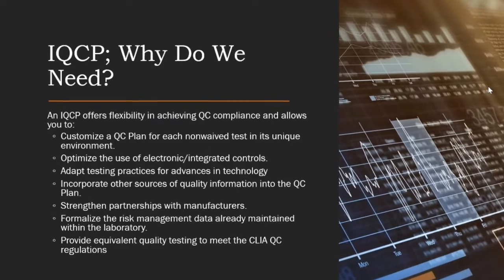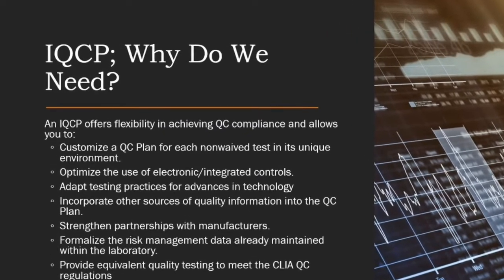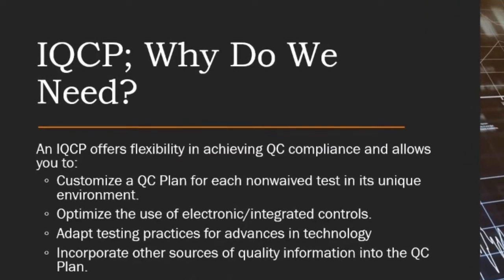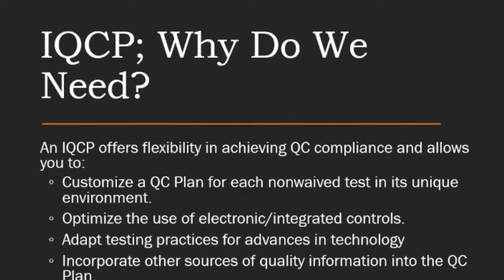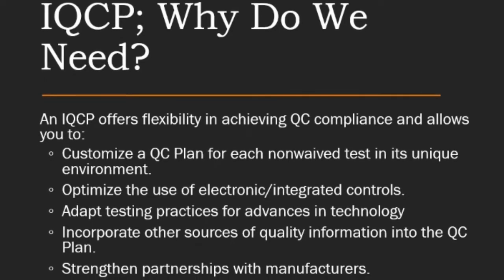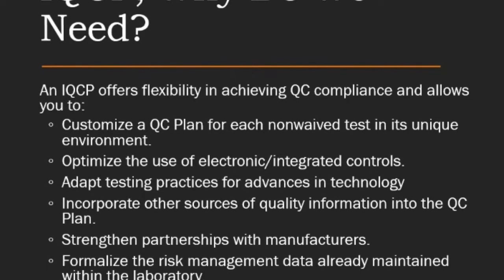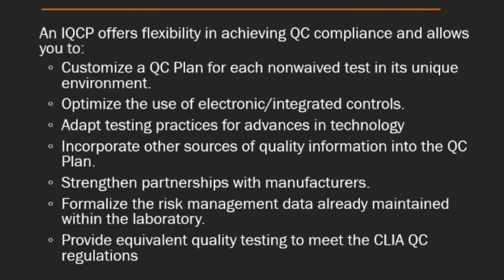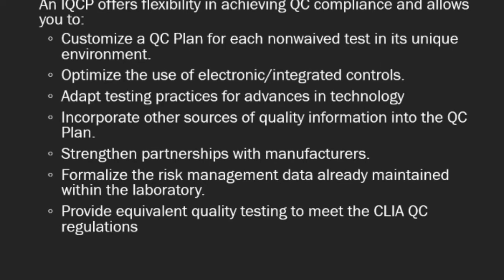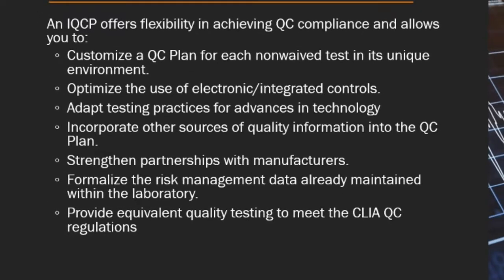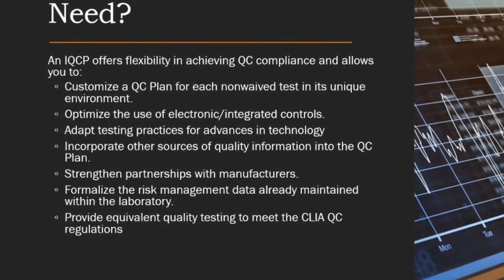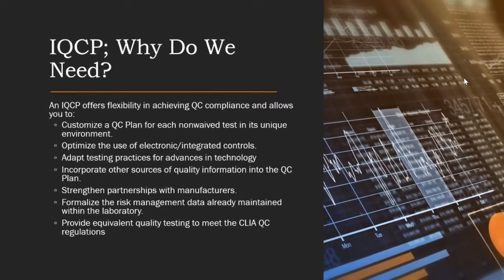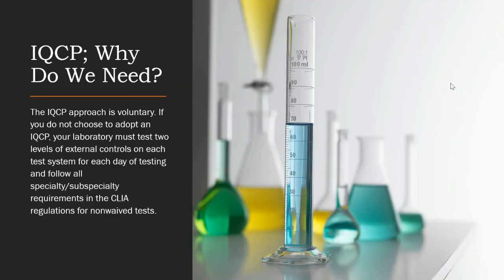An IQCP offers flexibility in achieving QC compliance and allows you to customize a QC plan for each non-waived test in its unique environment, optimize the use of electronic and integrated controls, adapt testing practices for advances in technology, incorporate other sources of quality information into the QC plan, strengthen partnerships with manufacturers, formalize the risk management data already maintained within the laboratory, and provide equivalent quality testing to meet the CLIA QC regulations.